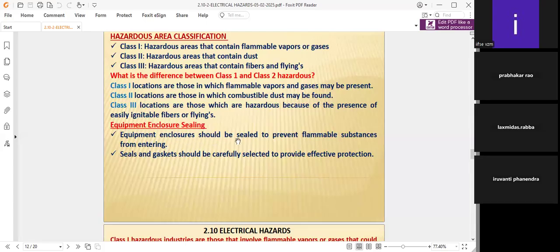Equipment enclosures should be sealed to prevent flammable substances from entering, because I have seen panel boards with a lot of leakage in remote areas where electrical panel boards are installed. After some time of opening and closing, the door lock gets loosened, and it is not sealed properly. Therefore, the substances in class 1, class 2, class 3 areas of industries, such as dust, will reach the circuit, and firing will occur. That's why it should be sealed properly.